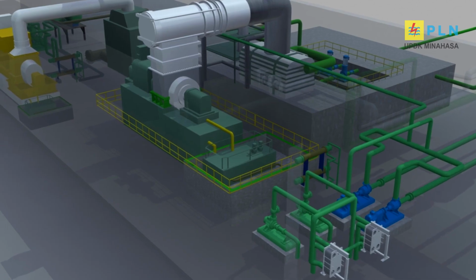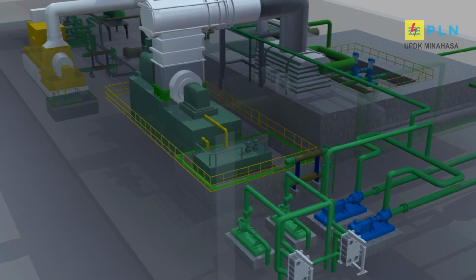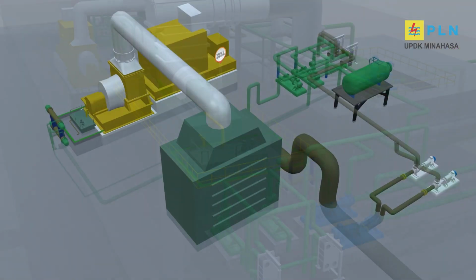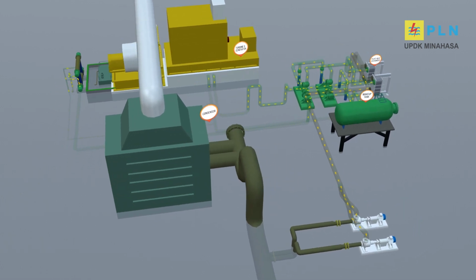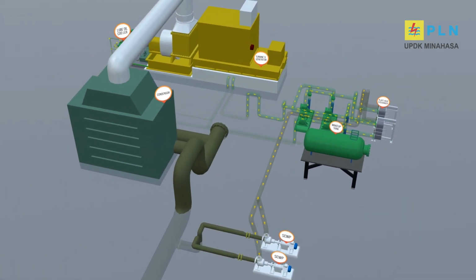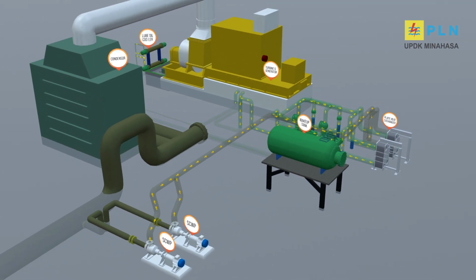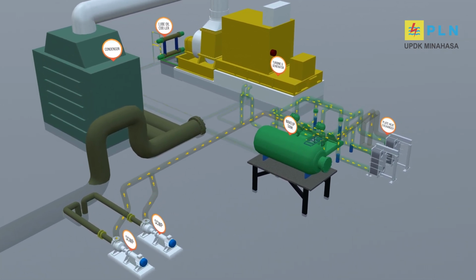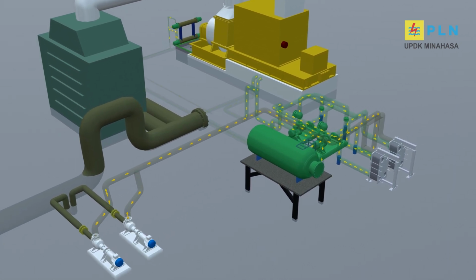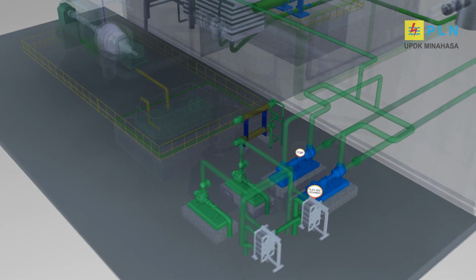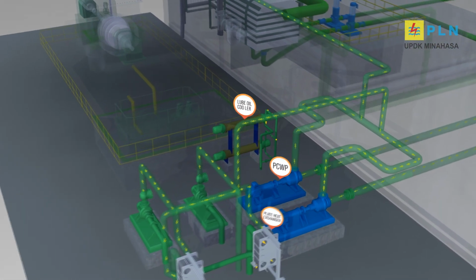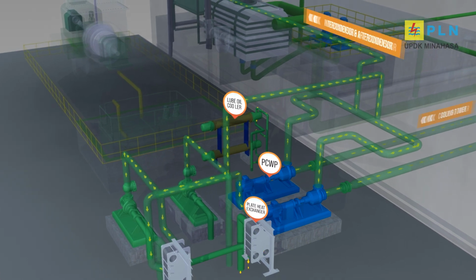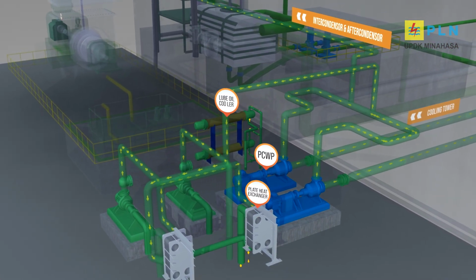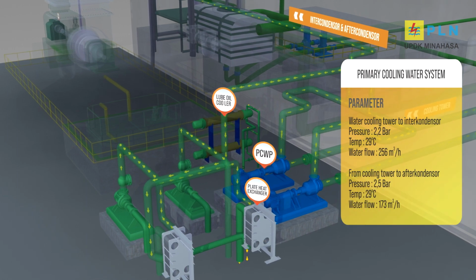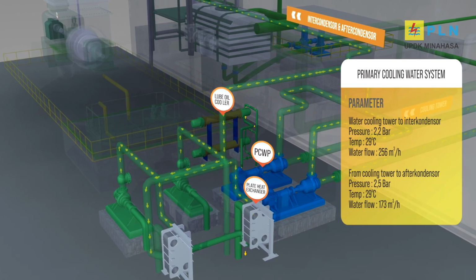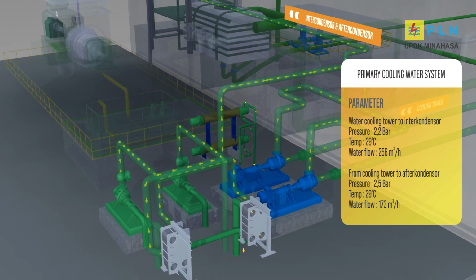Meanwhile, the auxiliary cooling system is divided into two, namely primary cooling and secondary cooling. For secondary cooling, the water from the makeup tank is circulated using a secondary auxiliary cooling water pump for cooling the generator cooler and lube oil cooler as a heat exchanger between lubricant and water. For primary cooling, water is circulated for the cooling process in the intercondenser and aftercondenser using water from the cooling tower, which is pumped using the primary auxiliary cooling water pump. Then the condensed water in the intercondenser and aftercondenser leads to the main condenser.